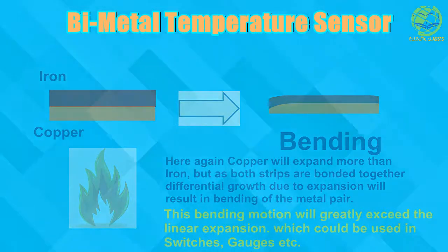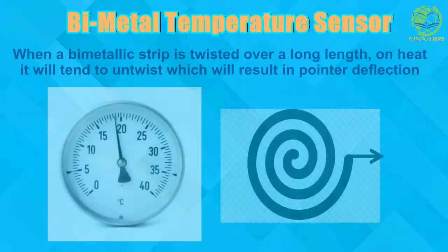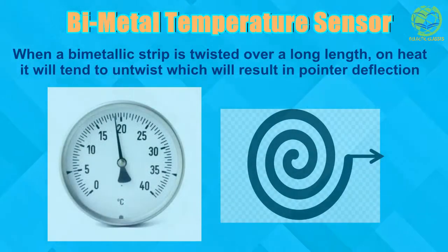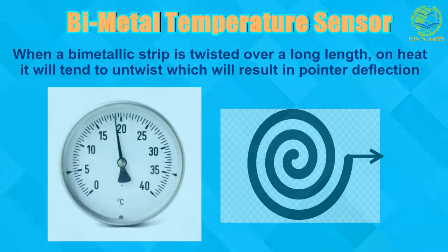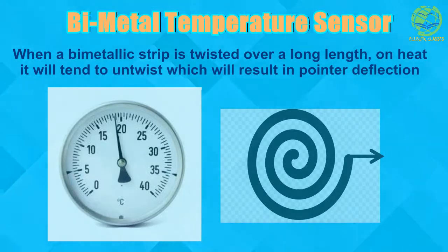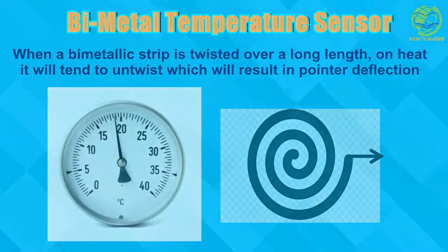The bimetal temperature sensor results in a bending motion with change in temperature. To use it in a temperature gauge, a bimetal strip is twisted over a long length and a pointer is attached at the outer end. With an increase in temperature, the twisted bimetal strip will try to untwist itself. During this untwisting mechanism, the pointer will deflect, and that is how a bimetal strip can be used to design a temperature gauge.